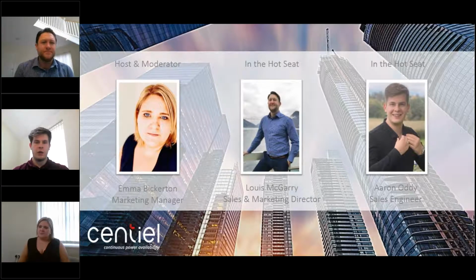Yeah, of course. So just to let everyone know, previously I was with a company who was still in the UPS industry, but more into the industrial side, looking at more robust systems and higher IP rating. Typically a UPS within a data center or a comms room is generally IP20 rating, just due to the clean environment, well air conditioned and at the right temperatures. These are more commercial UPS systems within the industry, rather than the more robust, high ingress protected designs that are made to order, really, and made to certain projects, which is needed for harsher environments. The more robust the equipment, essentially the longer it will last in harsher environments, as long as it's designed correctly.